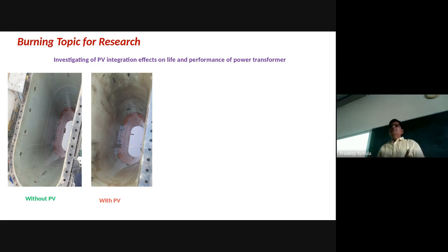The existing transformers, whatever I have installed in my plant 30 years back, when I connected PV to this transformer and opened it after 7 or 8 years, I have seen some degradation or derating. That's why people are hesitating to take solar and inverters. Inverters with 6 pulse, 12 pulse, 24 pulse, we are reducing harmonics, but still there is a problem. If you leave this tank like this, the transformer will fail one fine day. Why does it happen? Harmonics and spikes in the system, because the output from the inverter is not a pure sine wave. It is complex, causing heating effect and other issues. What can you do about this?